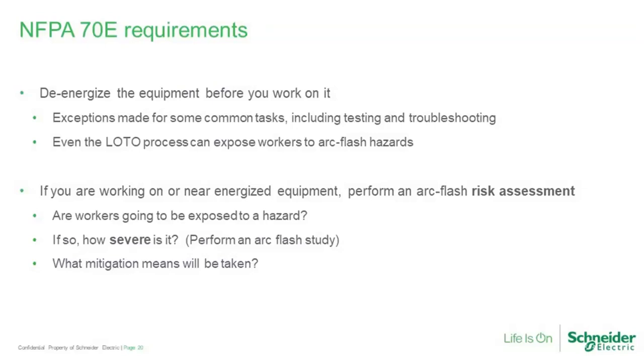NFPA 70E goes on further to define requirements for risk assessments. And again, here's kind of my summary of what you need to do with these arc flash risk assessments. Well, my take on it is that you answer three questions. Number one, are workers going to be exposed to a hazard? Just because you are around electrical equipment doesn't necessarily mean that you're exposed. Generally, to be exposed to an arc flash hazard, you have to be interacting with the equipment in a more direct manner. Pulling covers off certainly would do that.